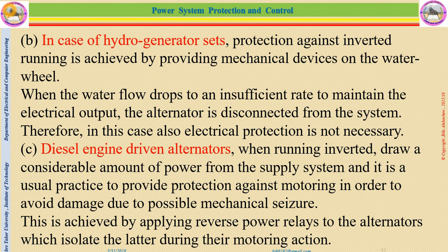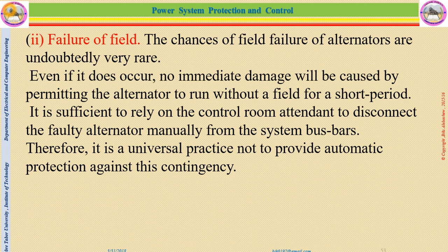When you see diesel engine driven alternators, when the running is inverted they draw a considerable amount of power from the supply system, and it is usual practice to provide protection against motoring in order to avoid damage to possible mechanical seizure. This is achieved by applying a reverse power relay to alternators, which may isolate the latter during their motoring action.